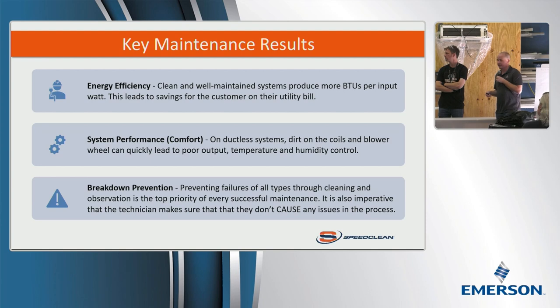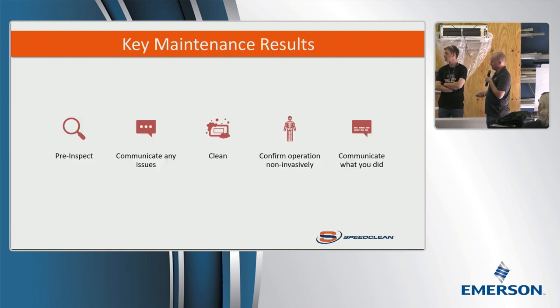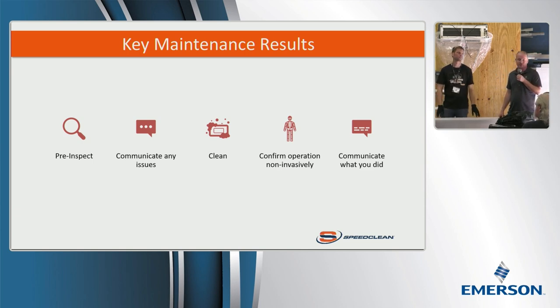If you keep them clean, they're not going to break down as much, which is also good. Also, if you keep them clean, it's less likely a junior technician will go there, find out it's not working, and rather than figuring out it's because of cleaning, put a bunch of refrigerant in it and mess the charge all up, which happens a lot with ductless systems. Ty's nodding his head because he knows, he teaches this. You go to a ductless system with a dirty blower wheel, dirty evaporator coil, whatever, and it's not working right, and they just start adding refrigerant because Freon is the answer to everything, or the TXV. Luckily these don't have a TXV, so they then replace the EEV with a TXV or a piston.